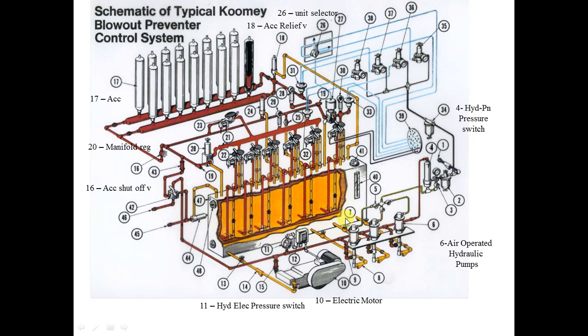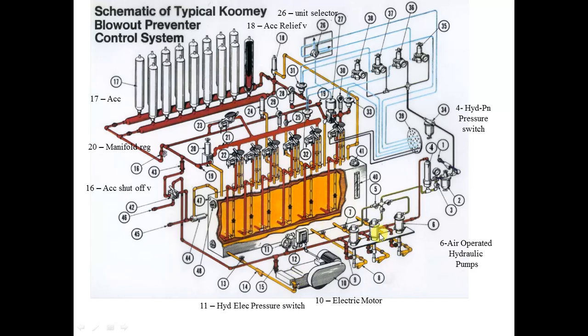If we close the air shutoff valve, we shut down the air pump in order to test the electric pump. There is also a shutoff valve for the electric pump, in order to test the air pump. These shutoff valves allow you to isolate and test either pump individually. Number six is the air pump, operated by air.